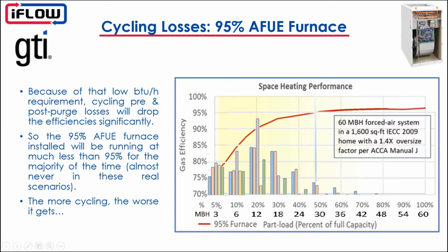lower input levels. So again, when we're operating at 5% of total input, which is 3,000 BTUs or 6,000 BTUs, you see the efficiency is quite low, starting at about 76-77%. Here at 10%, we're at about 85. When we hit 12%, we're up at about 90. And then we gradually ramp up to that 50% range where we actually hit the stated AFUE. So all to say that this is the MPG city that we were talking about earlier. This would be the MPG highway. So it does hit those numbers without question.